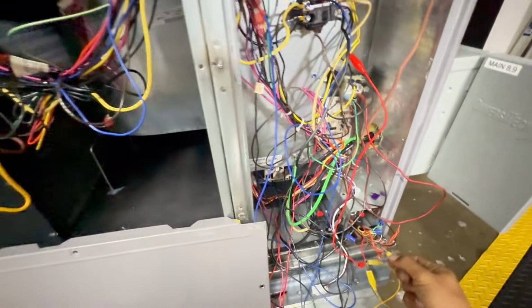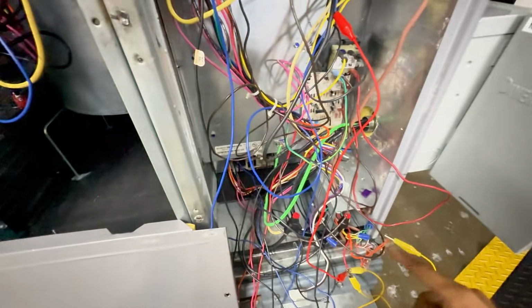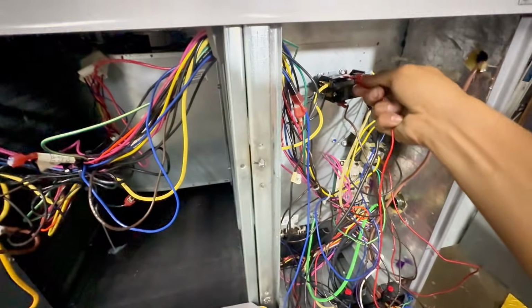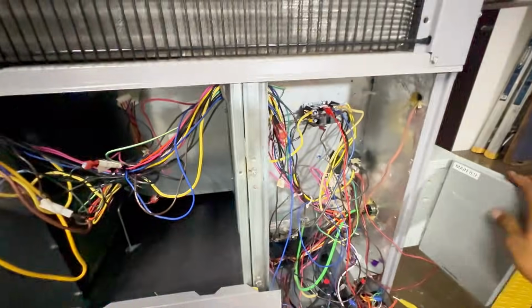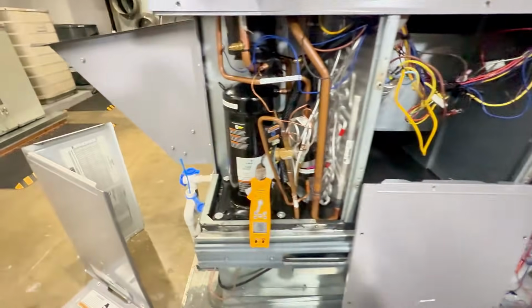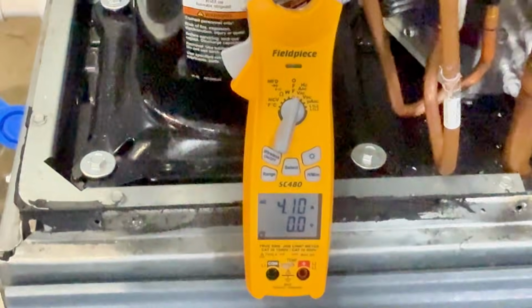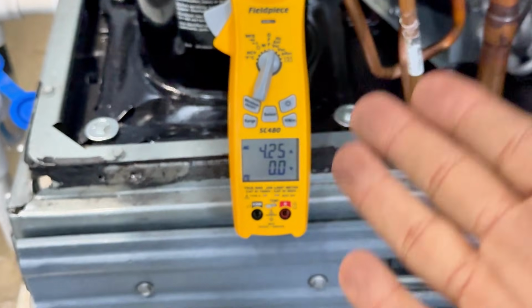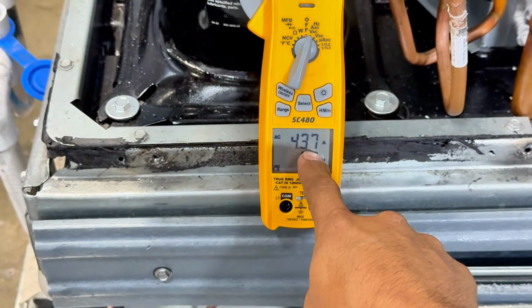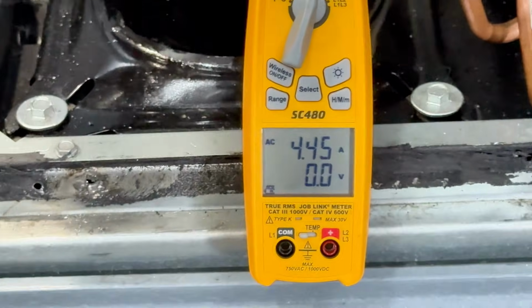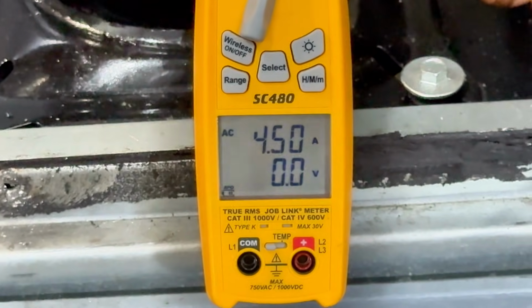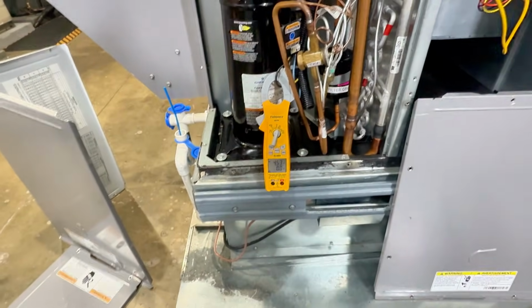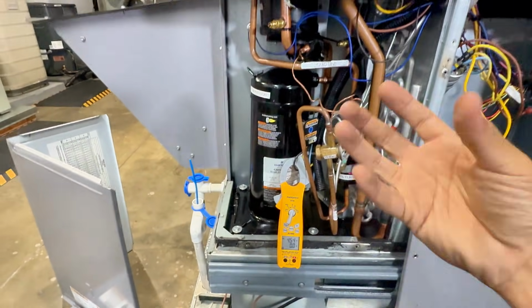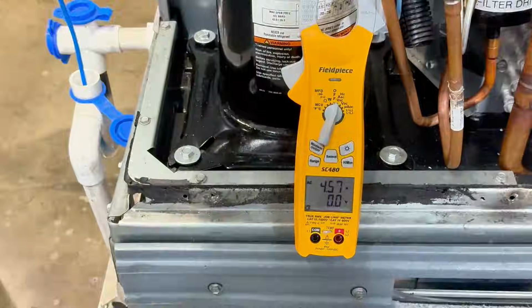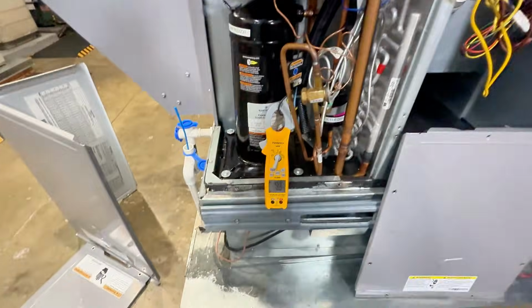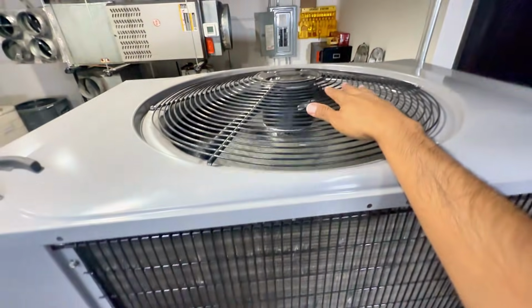It's a heat pump, so I have to send 24 volts to my reversing valve, and then send 24 volts to that contactor. So you see it turned on. You might not be able to hear it on your end, but I know you know it's on because it's pulling amps. We'll keep an eye on that. 4.5, and you're supposed to wait a little bit, about 10 minutes, so the compressor can pump and do its thing. So it's pulling 4.58. The condenser fan has turned on.